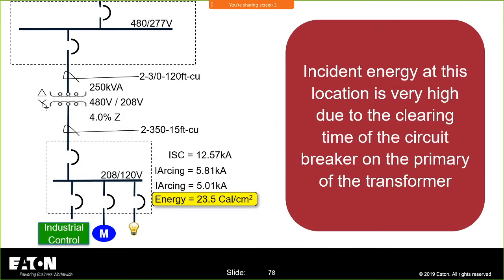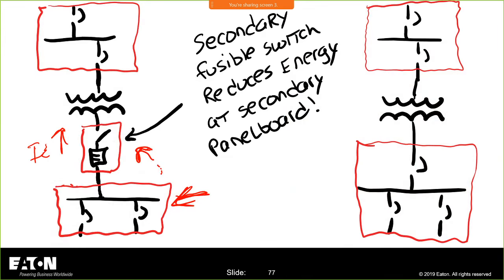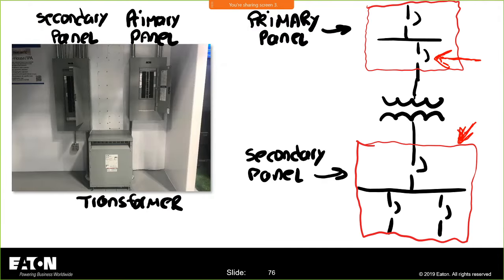So maintenance is more than just knowing the maintenance of the equipment. Maintenance could be considered keeping your one-line diagrams updated. So if I think my next upstream overcurrent device is a disconnect switch that's on the secondary of that transformer, and I'm relying on that, but in reality, it's more like this scenario where I have everything in one enclosure and my next upstream device is on the primary of that transformer.